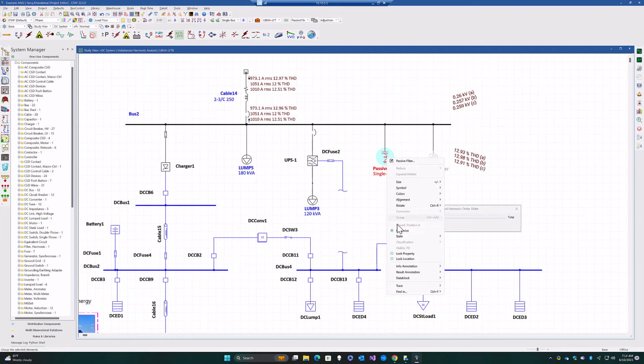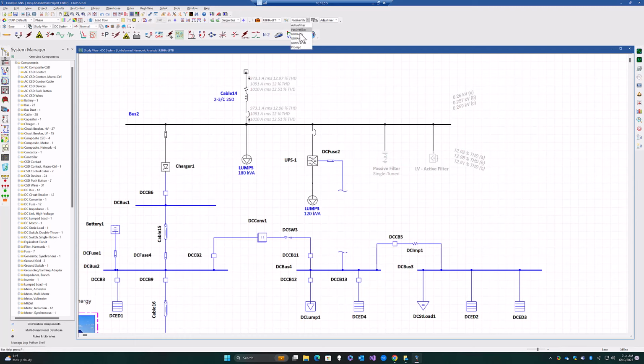So let's go ahead and turn this passive filter off again, and we'll go back to our active filter and turn the active filter on. Let's see what our active filter can achieve. It's actually able to bring the distortion down to 2% based on this 300 amps, and the voltage distortion also drops down significantly.